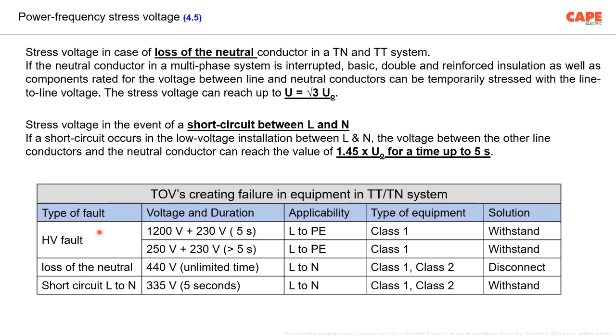In case of an industrial installation, the electrical designer shall ensure that the voltage applied to your equipment is limited to a level lesser than this particular stress voltage. This is number one. Number two, when you select your electrical equipment, you ensure that your equipment is able to withstand these voltages. So on one side, your design ensures that the voltage is limited to less than 1200 volt. On the other side, your equipment is able to withstand 1200 volt up to 5 seconds. So by this method, you are able to achieve safety.